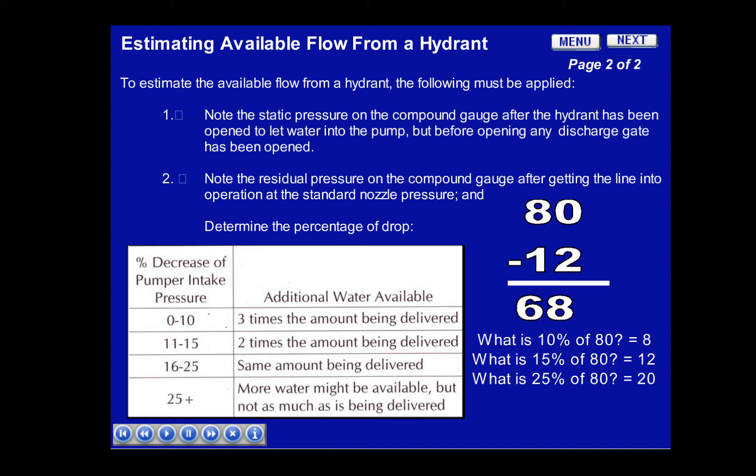The simple way to determine the percentage loss of your static pressure is to ask yourself: what is 10% of 80? In this case, that equals 8. Then simply take your answer and add half of 8, which is 4, and that'll tell us what 15% is. In the case of 80, 15% is 12. Then, to determine what the 25% loss is, you simply add 8 and 12 together, which equals 20. In the case of our sample of 80 psi, we had a loss of 15%, which was 12 psi. Based on the 15% loss, we would be able to supply two times the amount of water being delivered.